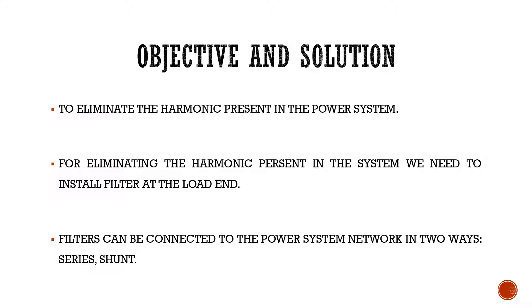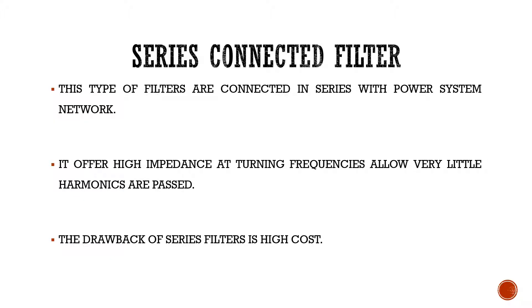We are going to see about the filter and working of the active power filter. The series connected filter — the name series itself denotes that the filter is connected in series connection with the power system. This kind of filter offers high impedance at tuning frequency, thus reducing the harmonics. It is capable of compensating the harmonic present in the system and allows only a lesser amount of harmonics to be passed to the power system.